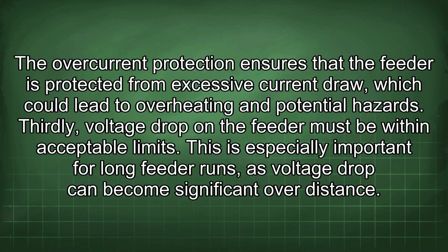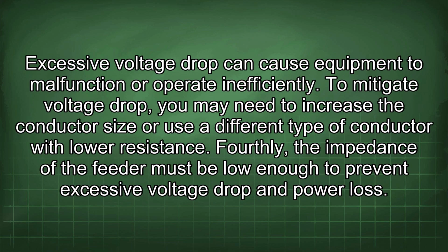Thirdly, voltage drop on the feeder must be within acceptable limits. This is especially important for long feeder runs, as voltage drop can become significant over distance. Excessive voltage drop can cause equipment to malfunction or operate inefficiently. To mitigate voltage drop, you may need to increase the conductor size or use a different type of conductor with low resistance. Fourthly, the impedance of the feeder must be low enough to prevent excessive voltage drop and power loss.